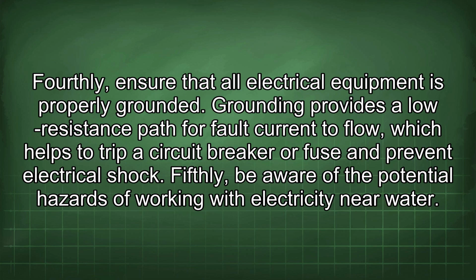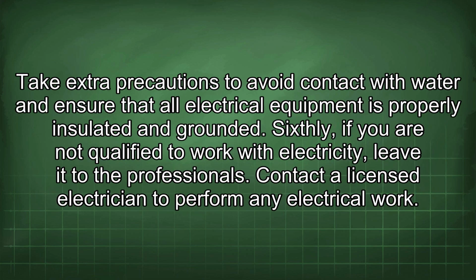Fourthly, ensure that all electrical equipment is properly grounded. Grounding provides a low resistance path for fault current to flow, which helps to trip a circuit breaker or fuse and prevent electrical shock. Fifthly, be aware of the potential hazards of working with electricity near water. Take extra precautions to avoid contact with water and ensure that all electrical equipment is properly insulated and grounded. Sixthly, if you are not qualified to work with electricity, leave it to the professionals. Contact a licensed electrician to perform any electrical work.